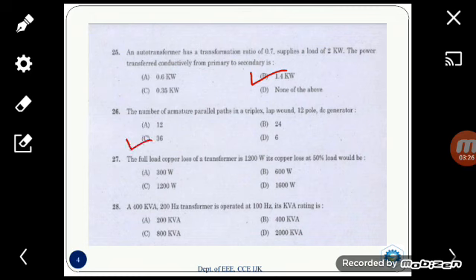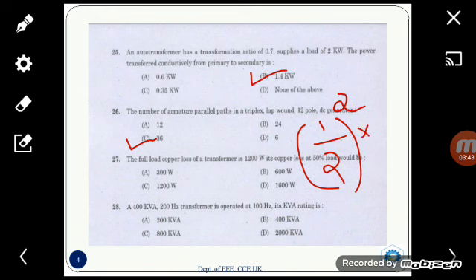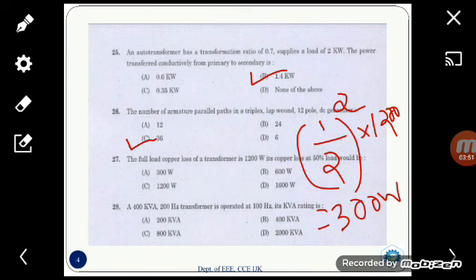The full load copper loss of a transformer is 1200 watts. Its copper loss at 50% load would be? Here the load is reduced by 50%, that is half. So the equation is (1/2)² × the full load copper loss, that is 1200 watts. We will get just 300 watts. So the answer here is 300, that is option A.